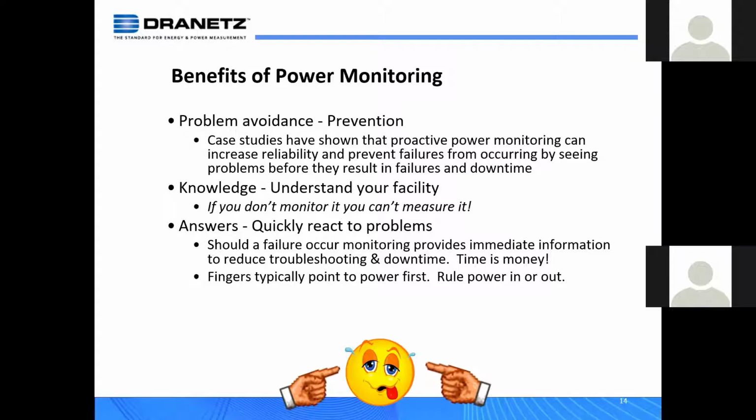So they notice that on our systems, and then they proactively schedule downtime for those UPS modules in a redundant system, so they can take them offline proactively and correct that problem, because they know that should they let it go, that module is going to fail at any time randomly in the future. They don't want that to happen. They want to keep their reliability up and going. Okay, so that's just one good example.